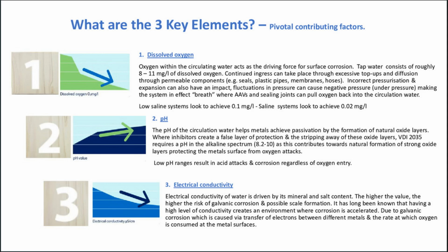So if we look at the pH, the pH of circulating water helps achieve passivation by the formation of natural oxide layers, where inhibitors create a false layer of protection and strip away these oxide layers. VDI 2035 requires a pH in the alkaline spectrum, so that's 8.2 to 10, depending on what your system metals are, as this contributes to the natural formation of strong oxide layer protection, protecting the metal surfaces from oxygen attacks. So low pH ranges result in acid attacks and corrosion regardless of oxygen entry.